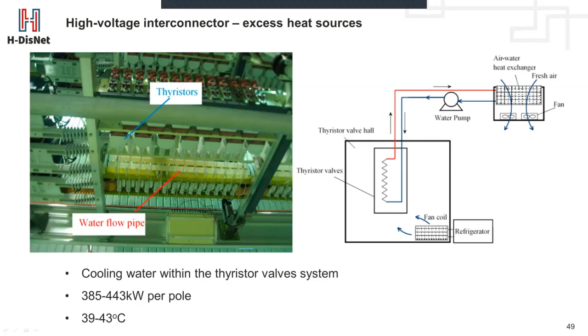One source is actually the cooling system for the thyristors. Water is pumped around this thyristor cooling set, at about 400 kilowatts per side. So there are two sides, so there's double that: about 800 kilowatts in total is available at about 40 degrees centigrade. So that's recoverable heat. And then the second source is across the transformer system.